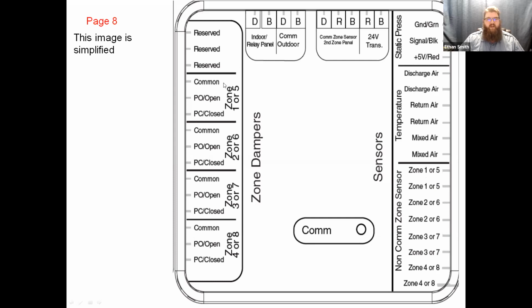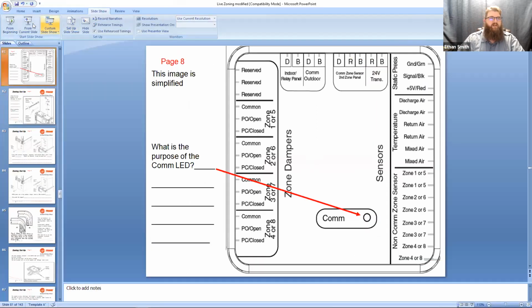Up on the left-hand side, we've got positions for all of your dampers. So we have our common wire, our power open, and our power closed terminals right there. So you're going to wire up those dampers right there. 3 wires. Not what I wanted to do.